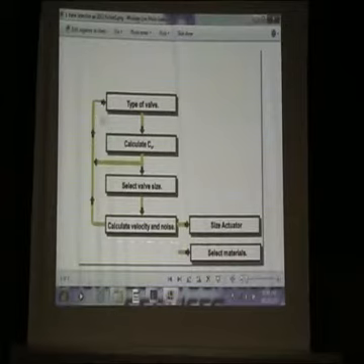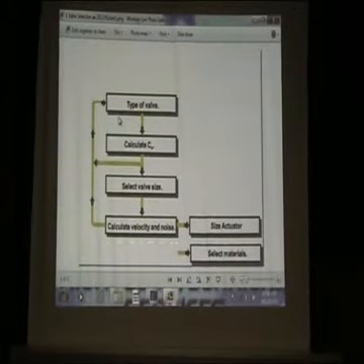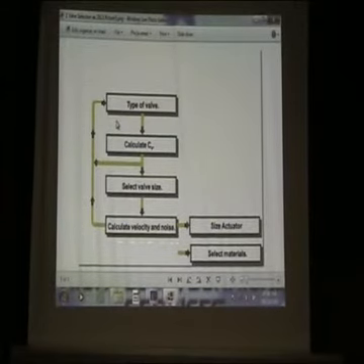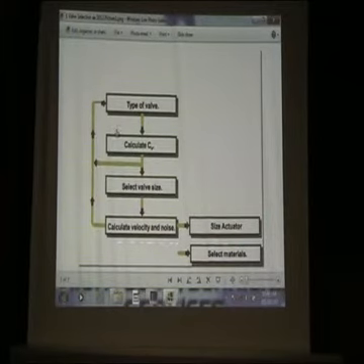But what I want to say is, the most important is, you ask the guys whether it's gas or liquids, the medium. The next thing you ask them is, is it clean or are there solids? Because after you've sized it and everything, you've selected a valve, and they tell you there's solids in it, the whole thing is down the drain because it's not going to work.